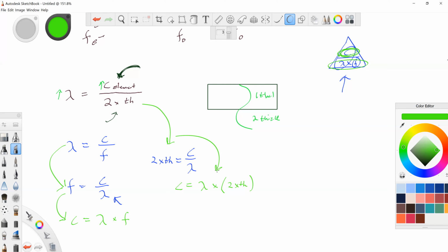But in any case, which of the following is most important in determination of the frequency of sound? Two characteristics that determine the frequency of sound of a pulse are thickness and the propagation speed in the crystal. The speed and impedance of the matching layer and the thickness of the backing material are unrelated to the frequency of an ultrasound pulse.